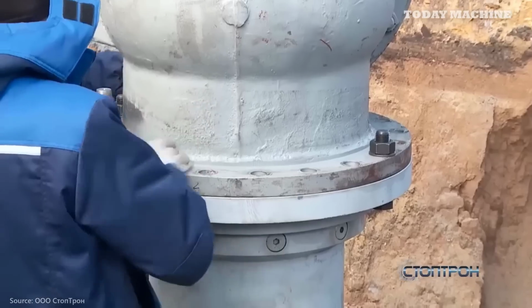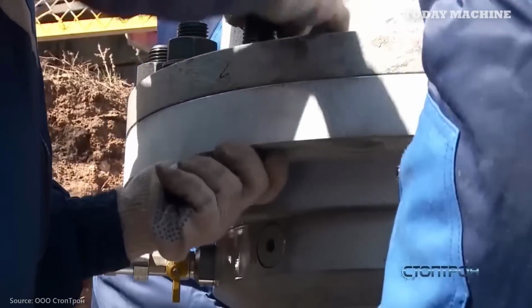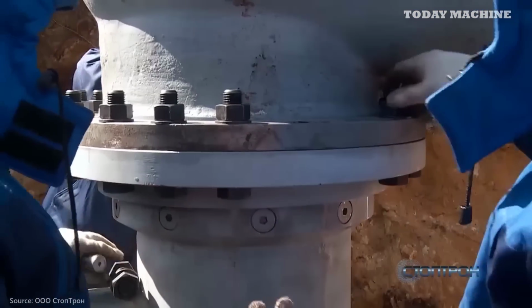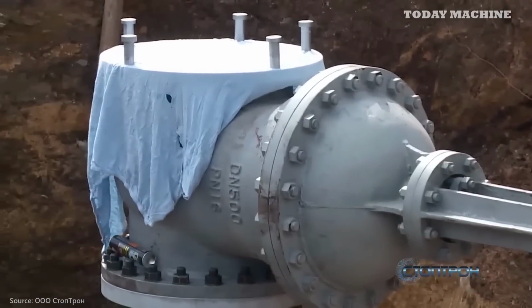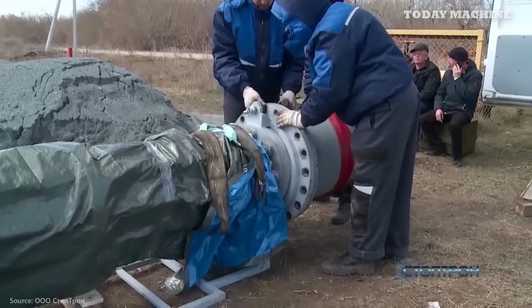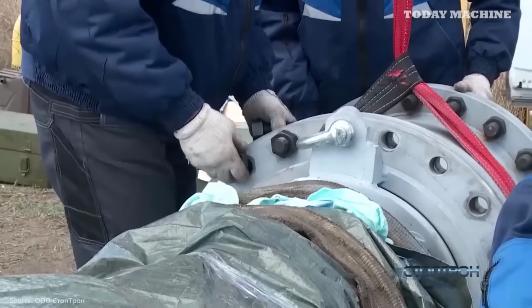Cutting operations. Using the drilling machines, purging fittings are cut, and pressure is equalized in the DN500 drilling machine through high-pressure hoses. The machine is then pressure tested to ensure integrity before the main pipeline cutting begins.